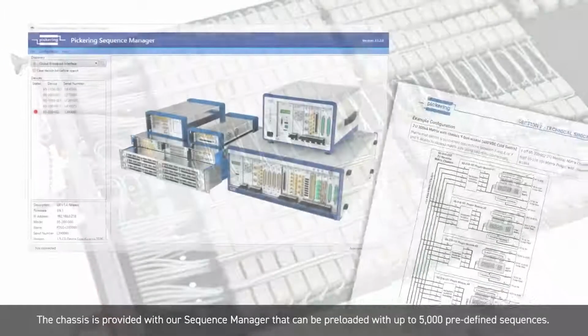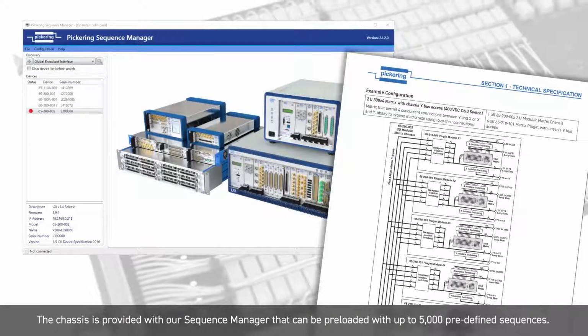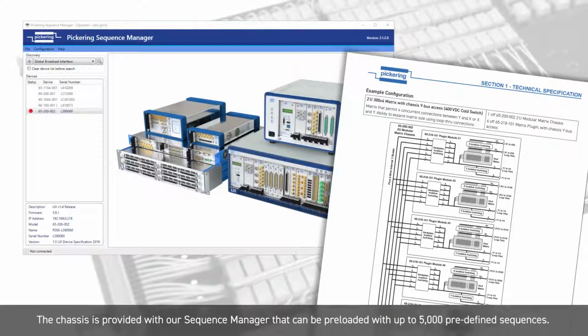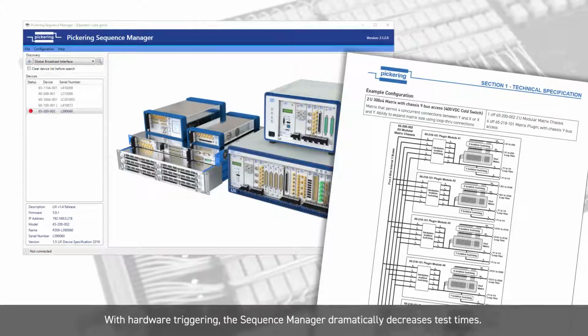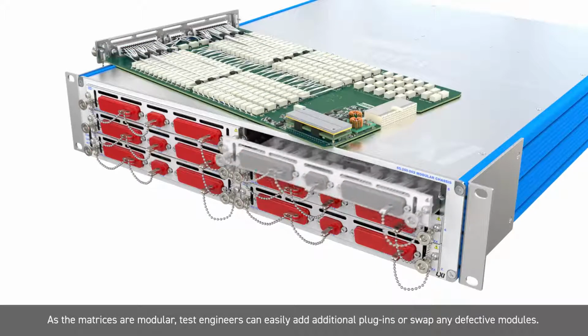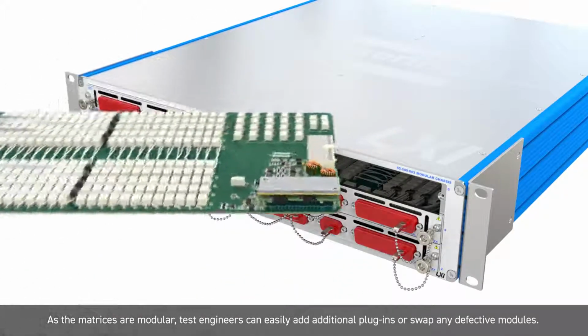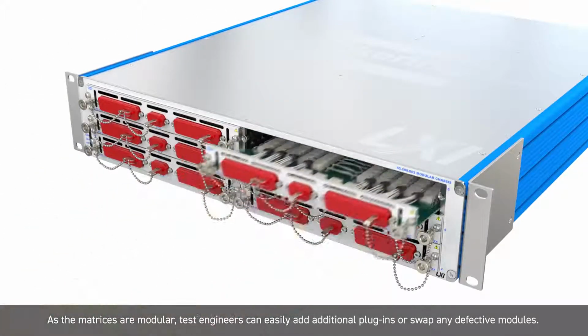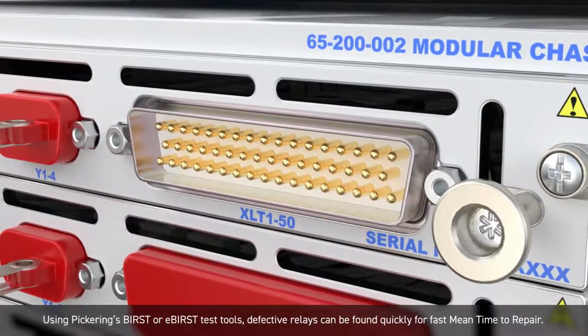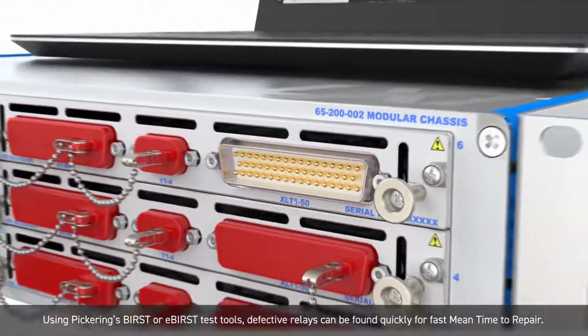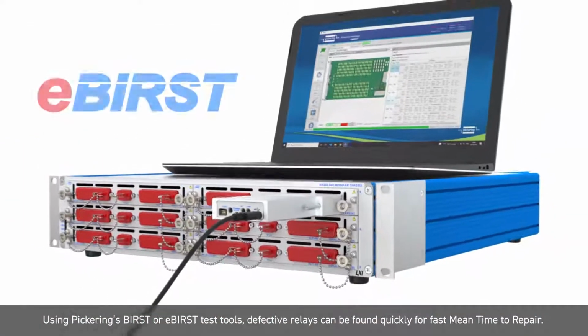The chassis is provided with our sequence manager that can be preloaded with up to 5,000 predefined sequences. With hardware triggering, the sequence manager dramatically decreases test times. As the matrices are modular, test engineers can easily add additional plugins or swap any defective modules. Using Pickering's BIRST or eBIRST test tools, defective relays can be found quickly for fast mean time to repair.